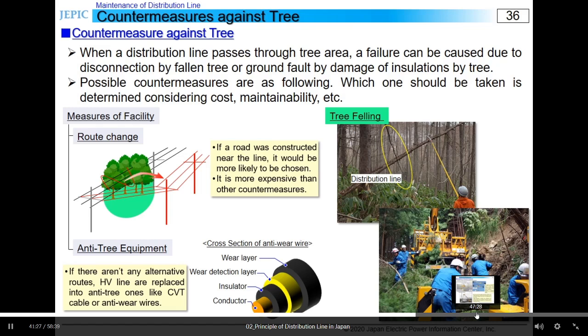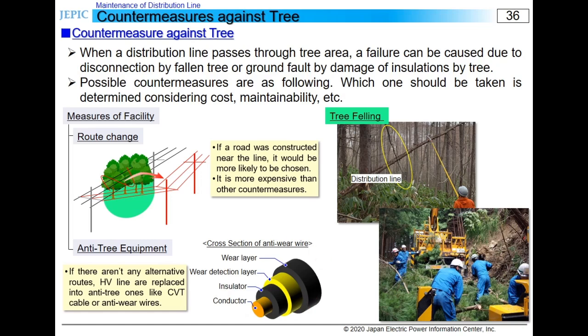Another measure of facility is to upgrade equipment, for example, using an anti-wear wire which is stronger against friction with trees. The cross-section of anti-wear wire is shown in this figure. It has a wear layer and a wear detection layer as additional layers, so it's less likely that the conductor is exposed than with normal insulation wires. If it's been worn out and the yellow wear detection layer is exposed, we can recognize it's time to be replaced.